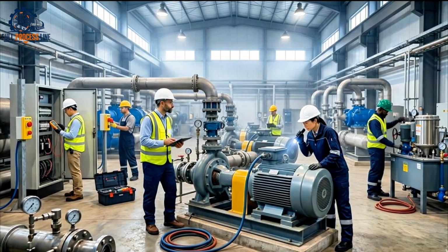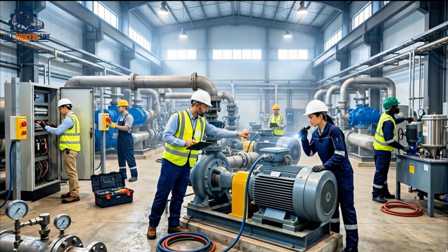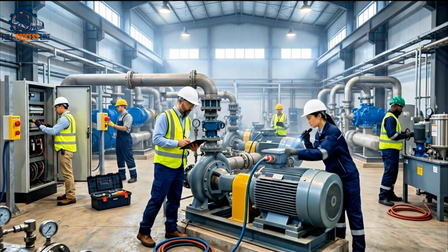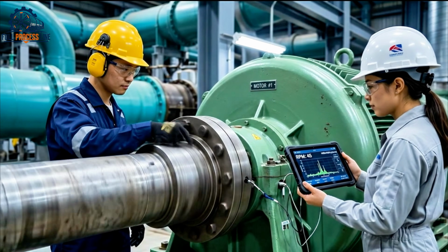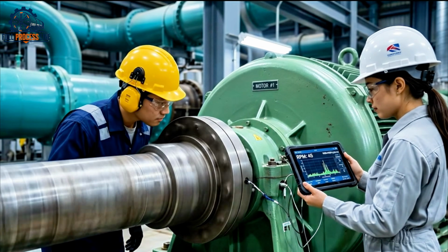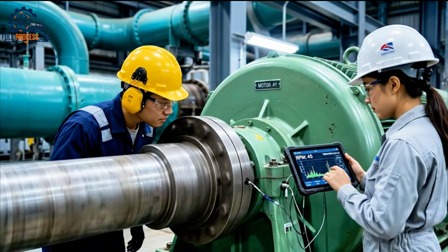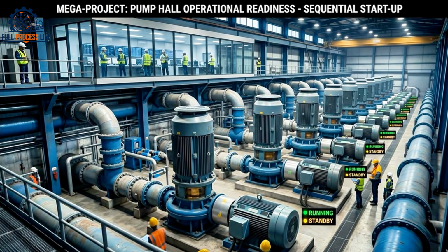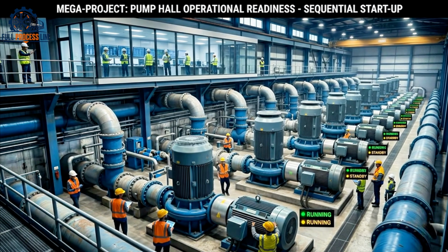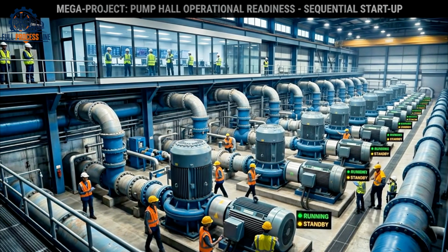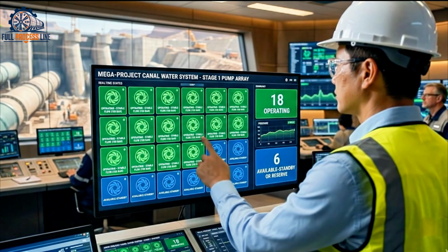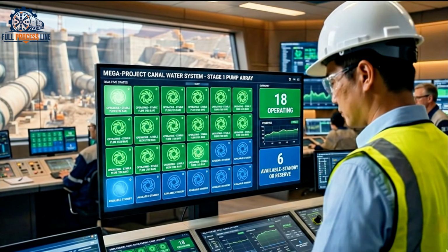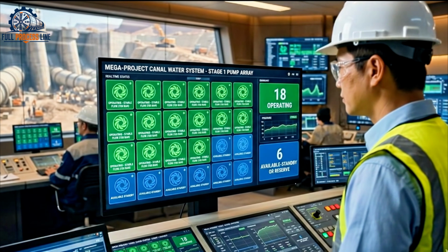Commissioning starts slowly, verifying every mechanical, electrical, and hydraulic protection system. Individual pump runs establish baseline vibration, temperature, current, and bearing behavior. One by one, more machines join without producing unacceptable electrical or hydraulic transients. The principal trial operates 18 units, while additional machines remain available for system flexibility.